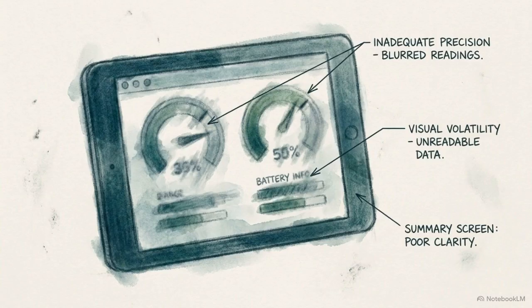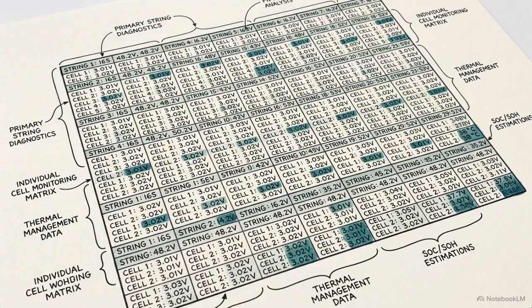Because of that volatility, the UPS interface alone is not enough. You must transition to the Battery Management System, the BMS. This is the absolute diagnostic authority for energy storage.